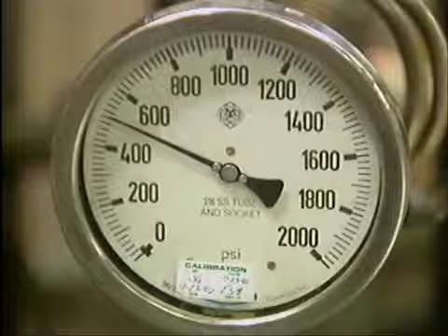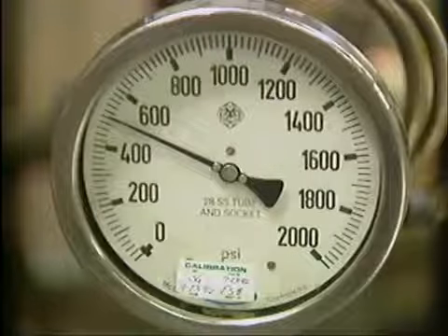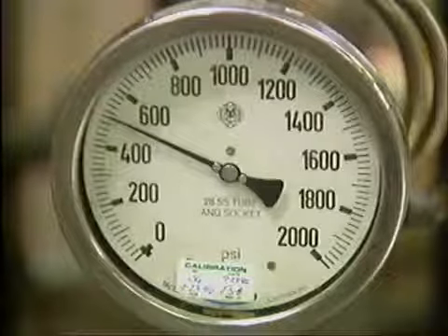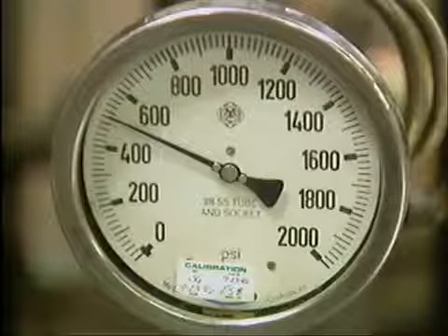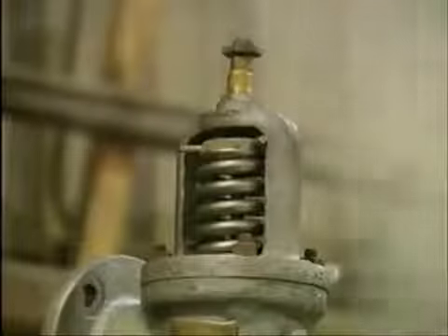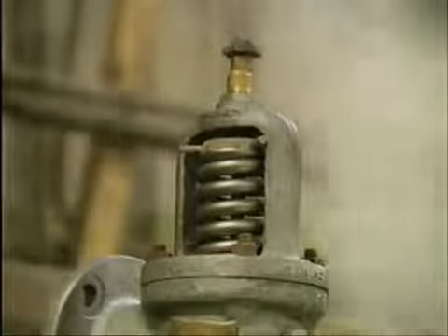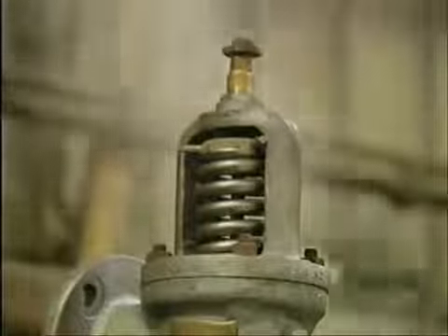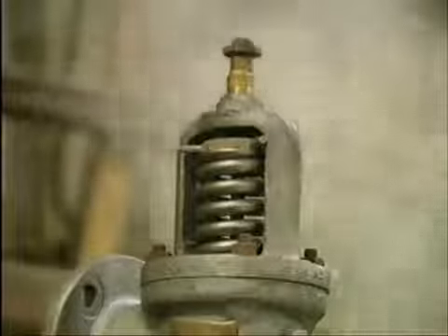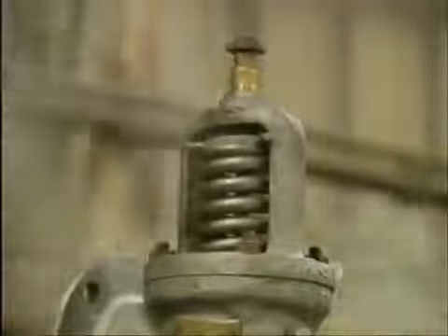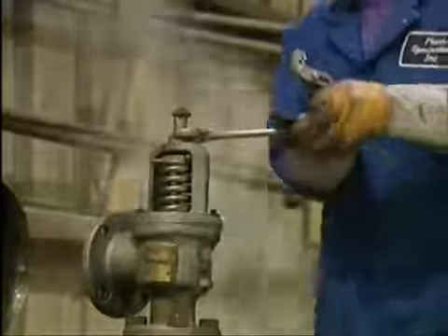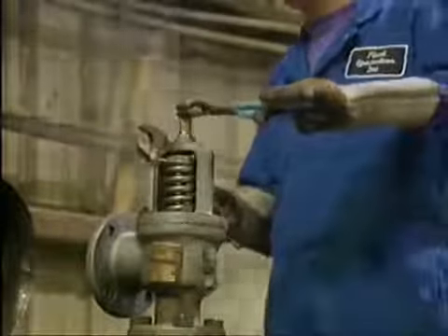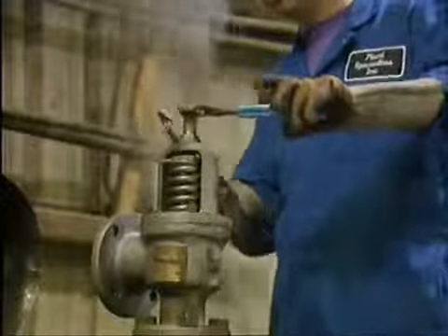In any case, when you're testing popping pressure, you're checking whether the valve opens when it's supposed to. If it opens too soon or too late in relation to the valve's set point, you must make adjustments. For this huddling chamber safety valve, you make set point adjustments by turning the compression screw. But before you can do that, you must lower the pressure so that there's no chance of the valve's opening accidentally while you're working on it. You must also break the lock nut free. If you try to turn the compression screw without loosening the lock nut, you'll probably damage the screw.